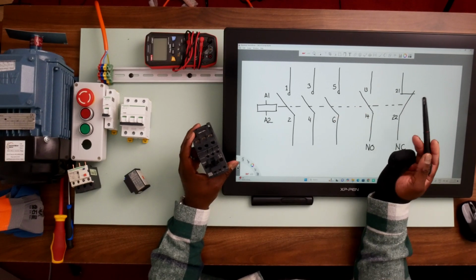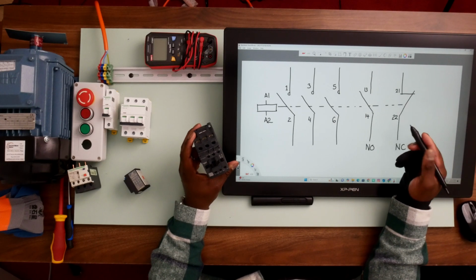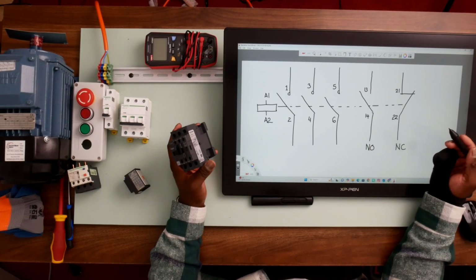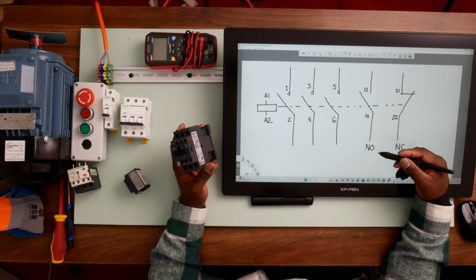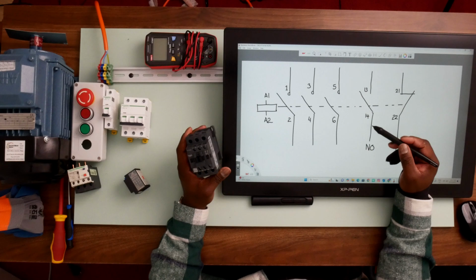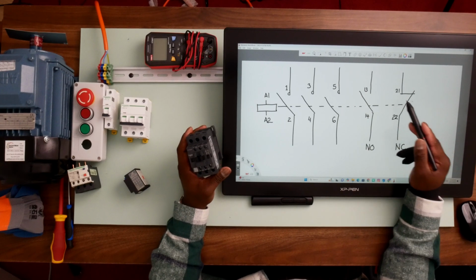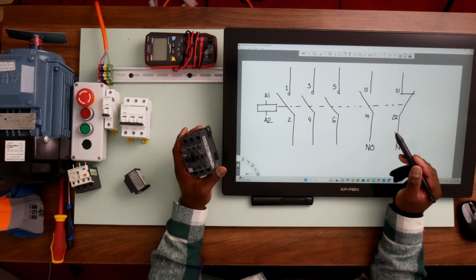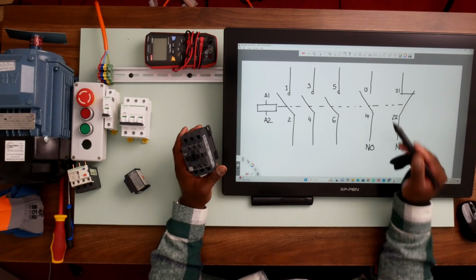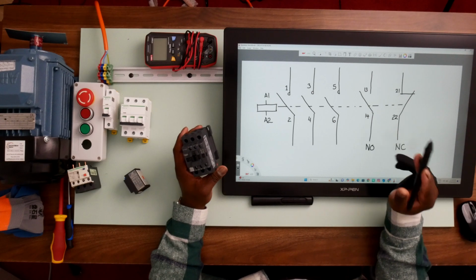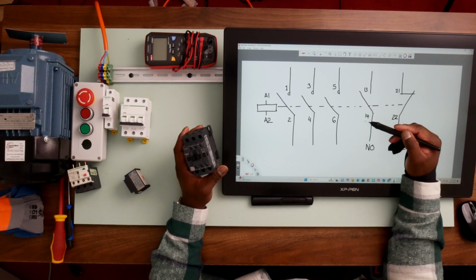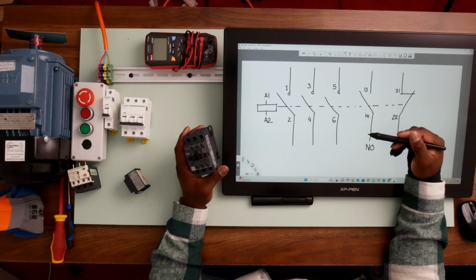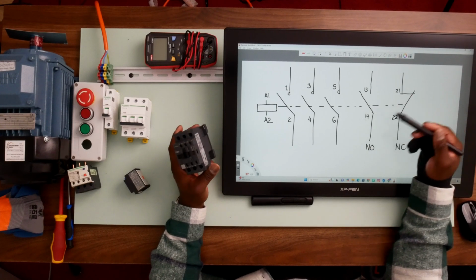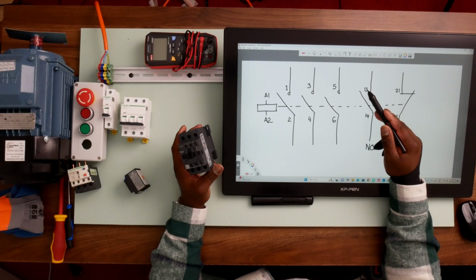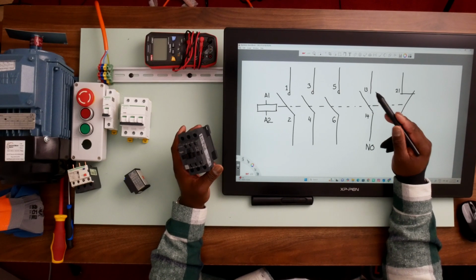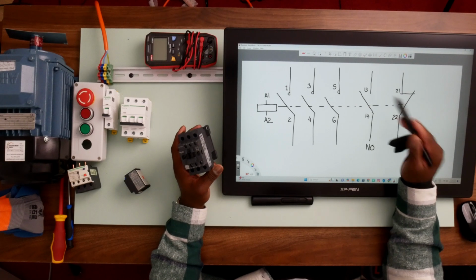The coil also operates the auxiliary contacts, which can be built in or clip-on onto the contactor. The normally open contacts that we have here are 13 and 14, and the normally closed contacts that we have here are 21 and 22. And remember what we mentioned about normally open contacts: they always come in combinations of numbers that end in 3 and 4. It could be 3 and 4, 13 and 14, 23 and 24, or 53 and 54, as long as the least significant numbers are 3 and 4. Then that tells you that it's a normally open contact.